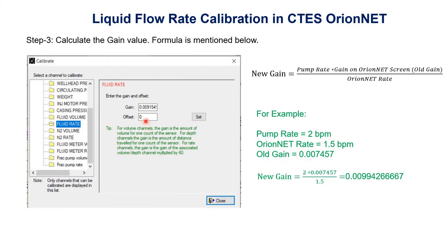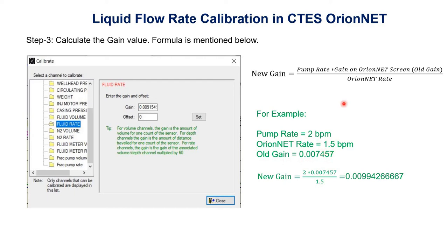Here we have gain and offset. We have to calculate the new gain. The formula for new gain is: pump rate multiplied by the old gain (shown on the Orion Net screen), divided by the Orion Net rate. For example, assume the pump rate is 2 barrels per minute, the Orion Net rate is 1.5 barrels per minute, and the old gain is 0.007457. So new gain = 2 × 0.007457 / 1.5 = 0.009942.